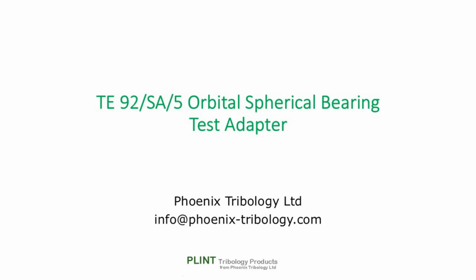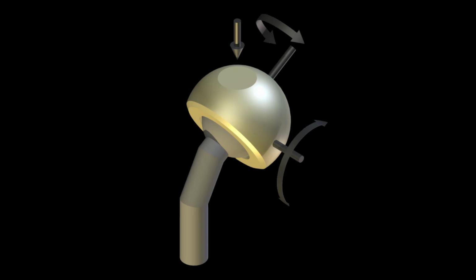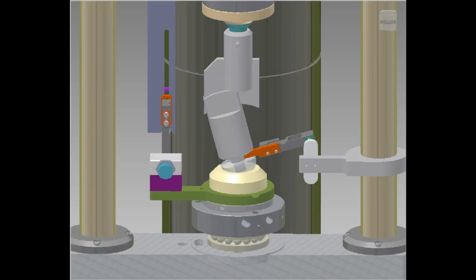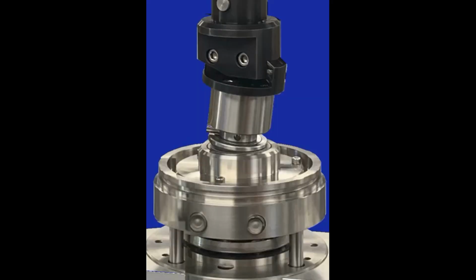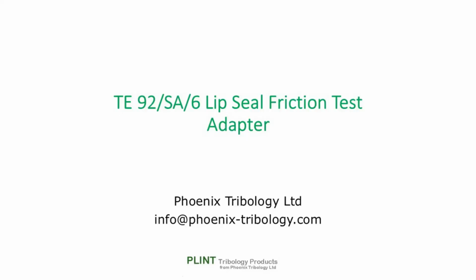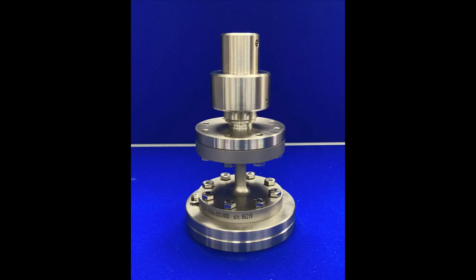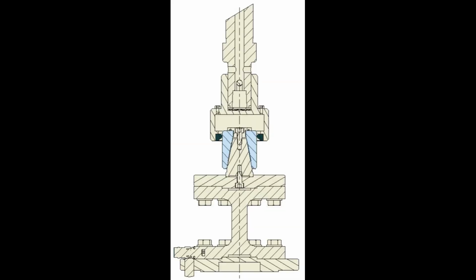The orbital spherical bearing test adapter is for measuring the friction vectors on mechanical and human joints subjected to orbital motion. The lip seal adapter is for measuring lip seal friction and for observing leakage past the seal.